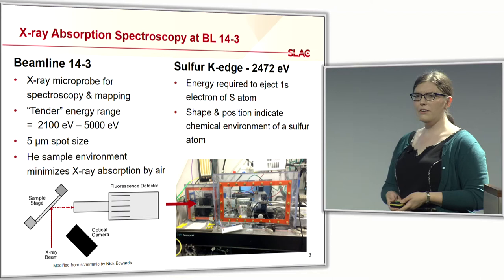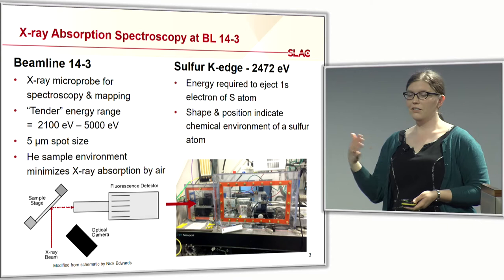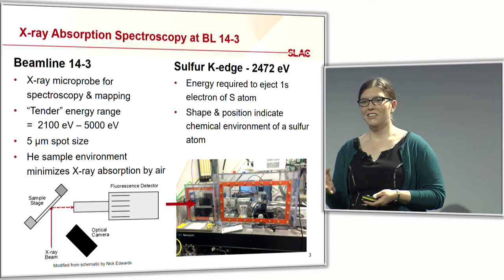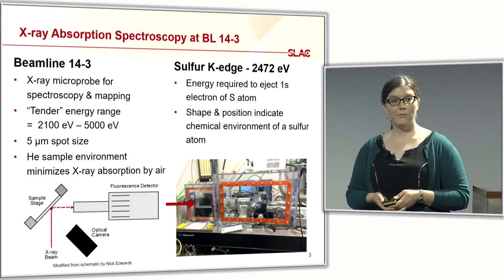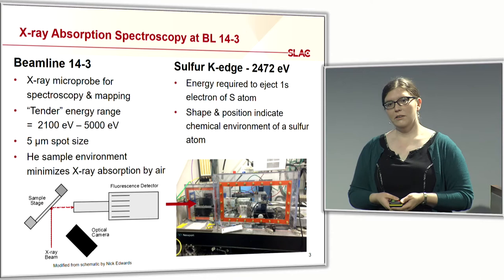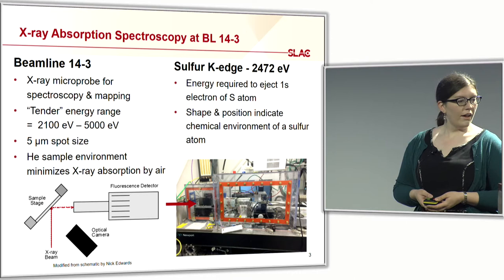Beamline 14-3 is an X-ray microprobe in the tender X-ray regime, which is about 2,100 eV to 5,000 eV. Above that you have hard X-rays, below that you have soft X-rays, and in the tender range in between — it makes me think of a nice steak: tender, well-done X-rays, rare X-rays. What's unique about this beamline is we have a very small spot size — five microns — so we can get very high spatial resolution, and we also have a helium sample environment to prevent X-ray absorption from the air.